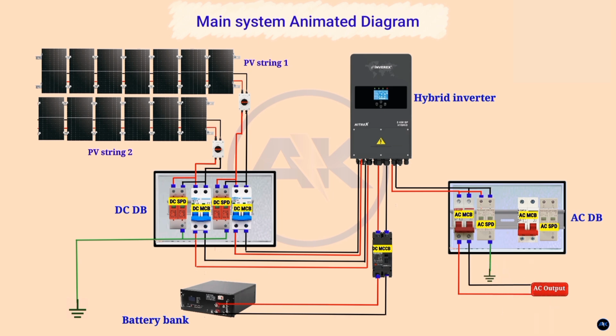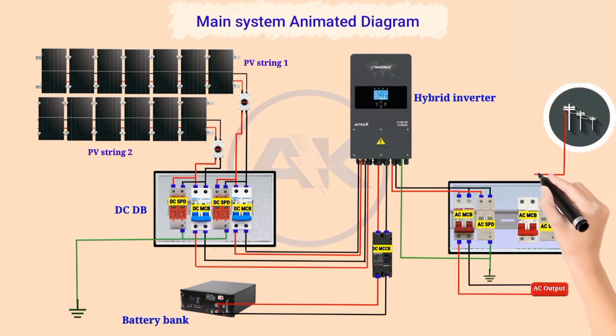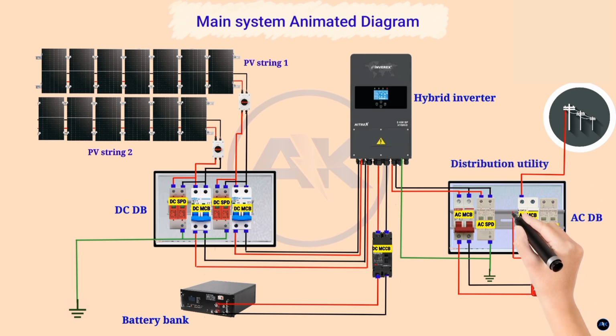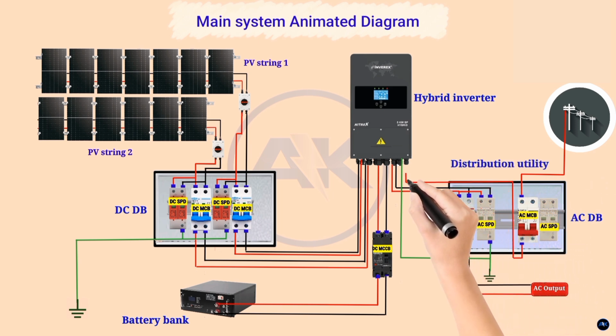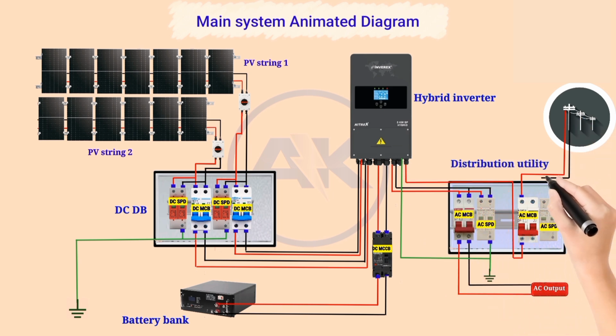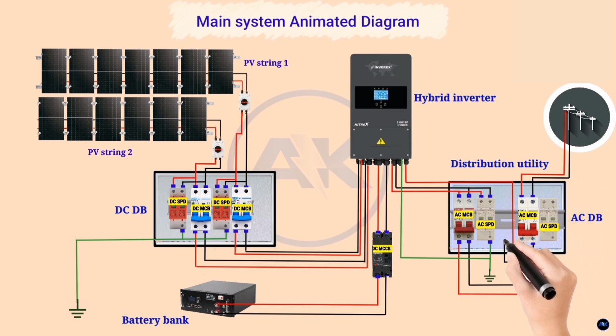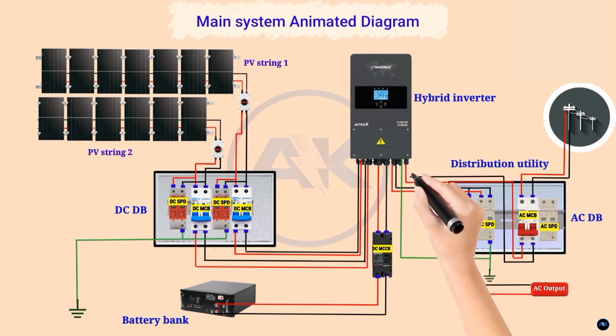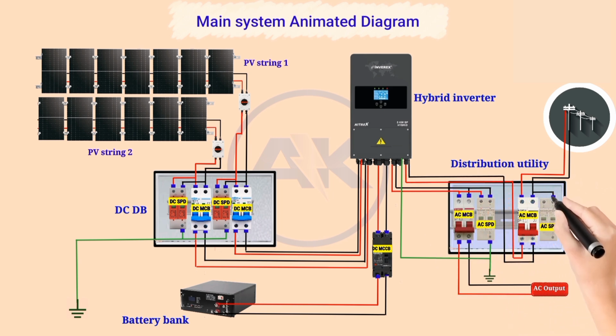We can connect the AC/SPD ground to the bus bar, which is also connected to our ground rod. And the same thing with the chassis of the hybrid inverter. Now working on our grid connection, this one goes to our AC/MCB, and that is from our distribution utility. That is for the AC input of our hybrid inverter.